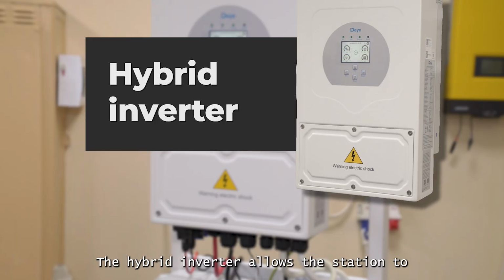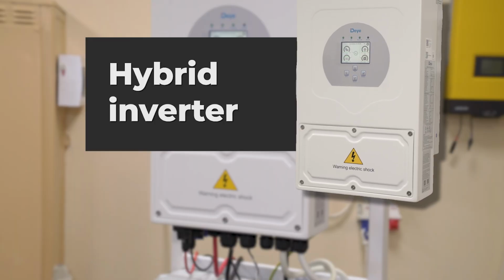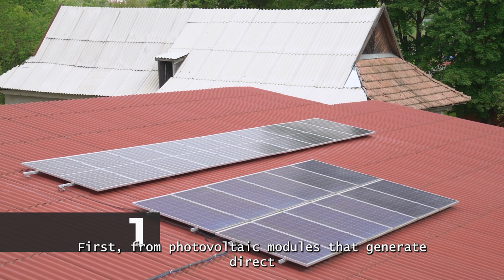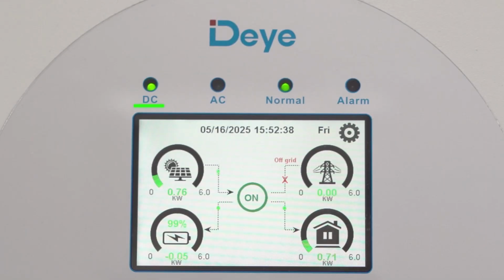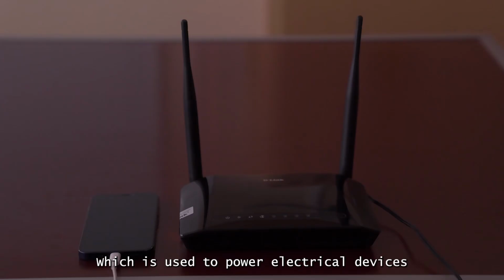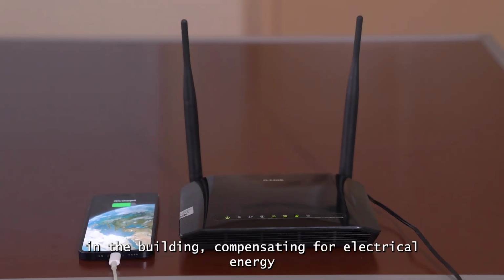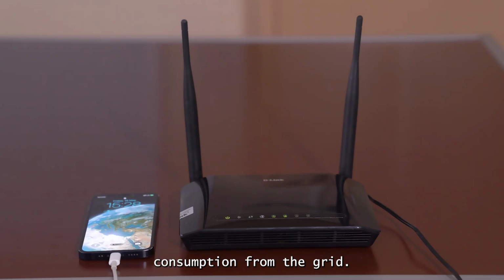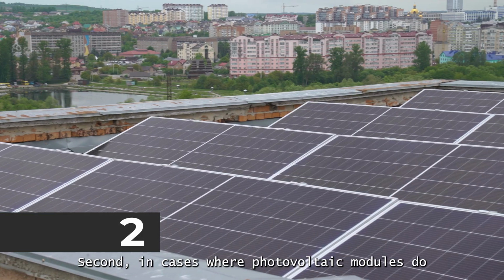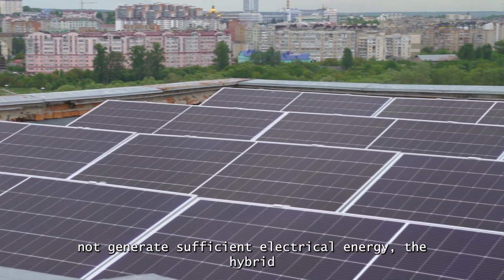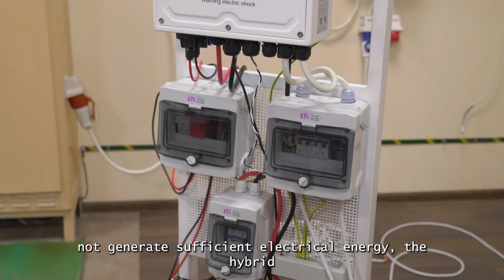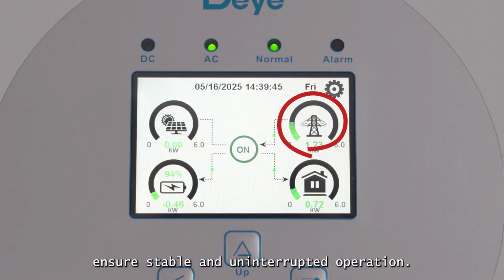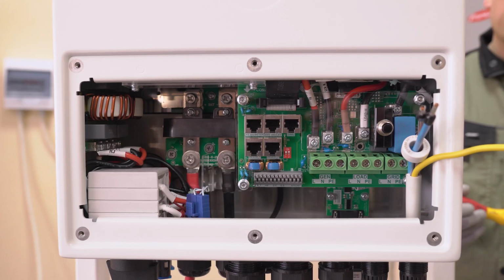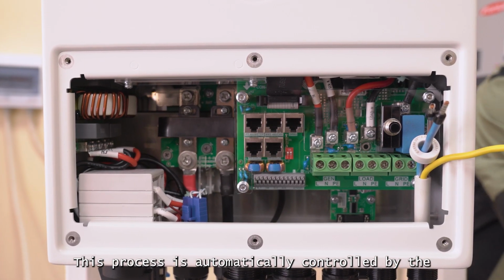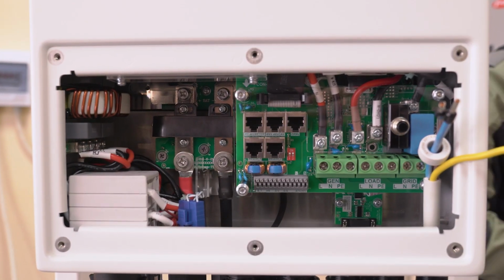The hybrid inverter allows the station to operate in several modes. First, from photovoltaic modules that generate direct current, DC, the hybrid inverter converts it to alternating current, AC, which is used to power electrical devices in the building, compensating for electrical energy consumption from the grid. Second, in cases where photovoltaic modules do not generate sufficient electrical energy, the hybrid inverter switches to the input grid to ensure stable and uninterrupted operation. This process is automatically controlled by the built-in controller of the hybrid inverter.